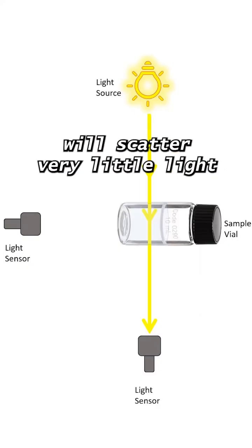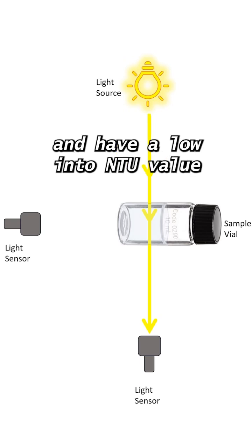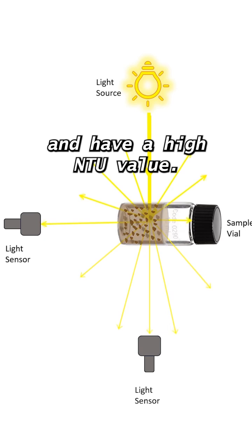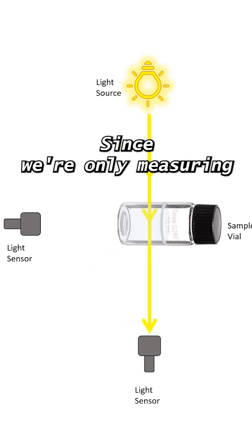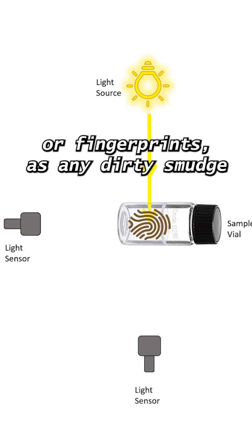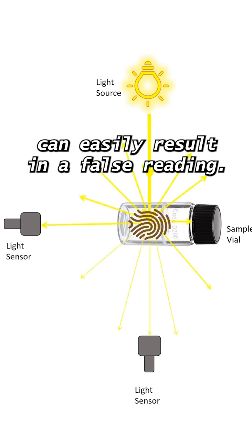Samples with low turbidity will scatter very little light and have a low NTU value, whereas samples with high turbidity will scatter more light and have a high NTU value. Since we're only measuring the amount of light that's reflected, we want to make sure our vial is free of scratches or fingerprints, as any dirty smudge can easily result in a false reading.